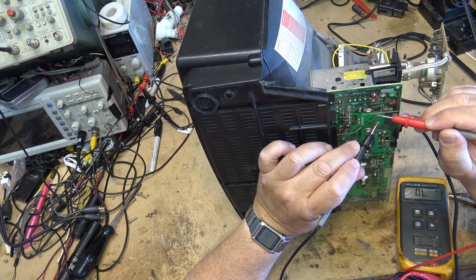Okay, still nothing. So we'll first check to see that we've actually got power getting to the set itself, which we do - as you can see, 120 volts, and we have 120 volts making it through that jumper that replaced the fuse. We should have power getting to the primary of the standby transformer, which we do, and we have 13 volts on the secondary. Excellent, so the transformer is not popped.